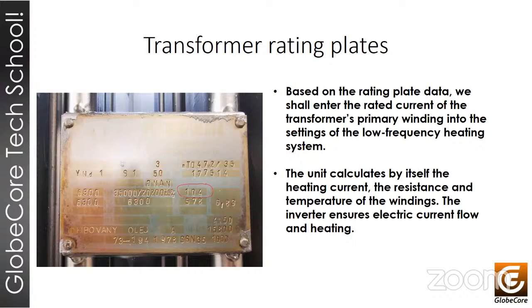As we mentioned above, the transformer is disconnected from the power line, and the power leads of the inverter and the measuring circuits of the ohmmeter are connected to the high voltage winding of the transformer. The low voltage winding is short-circuited due to magnetic bond and low frequency. The magnetic circuit is saturated and the windings are heated. The inverter periodically shuts off. The resistance and temperature of the heated windings are checked, and the transformer tank and the transformer oil temperatures are continuously monitored.